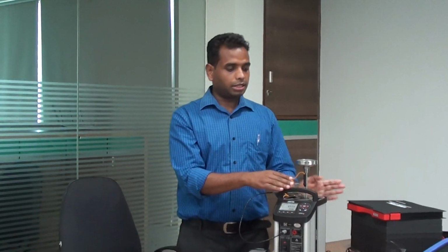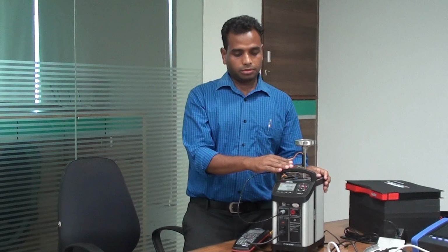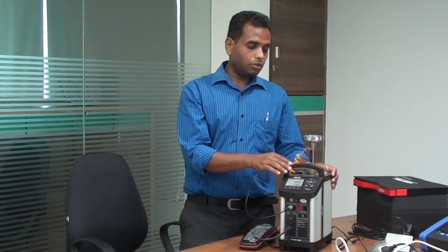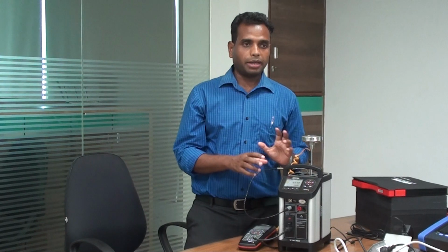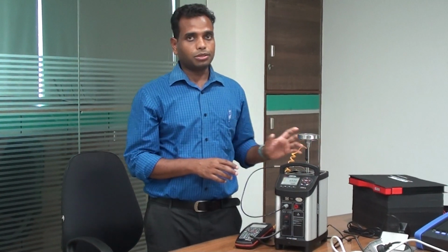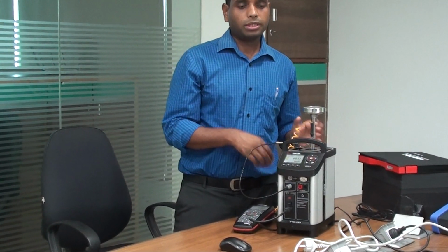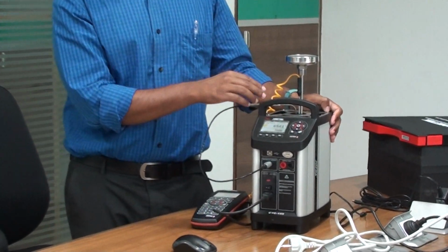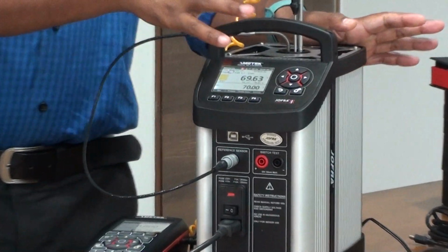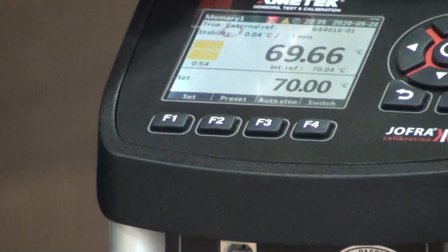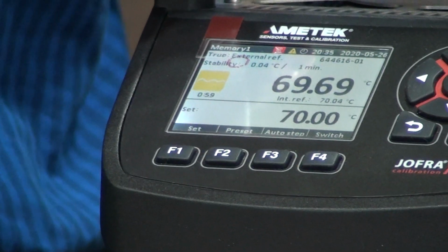I will add something about the JOFRA software. We can do this calibration through a PC by using the JOFRA software. We can use this D-type USB cable and connect it with the PC, and we can operate this instrument directly through the PC. You need not touch this. Only the physical settings have to be done manually, like setting the temperature sensors, DUT, all that. After that, once you leave the instrument and go to the PC, you do the calibration in the PC itself. That is given free of cost by JOFRA. And there is also a cloud software, which is on a charge basis.